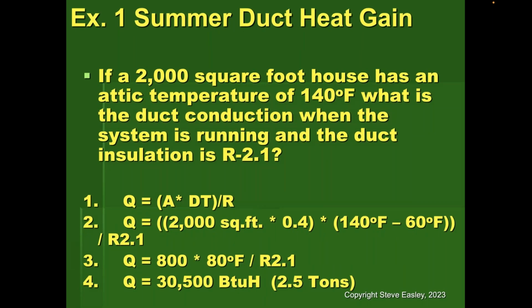Now let's take a look at summer heat gain, because this I think will really impress you in terms of some work that the California Energy Commission did a number of years back. They found that the average amount of square footage of ductwork in an attic ends up being about 40% of the floor area of your home. So if I have a 2,000 square foot house with my ducts in the attic, what kind of penalty is that? What I'm getting at here is that if we're trying to get summertime performance out of our heat pump air conditioning system, we need to pay close attention to one of the biggest kisses of death we can have in our system, which is having our ductwork up in our attic.